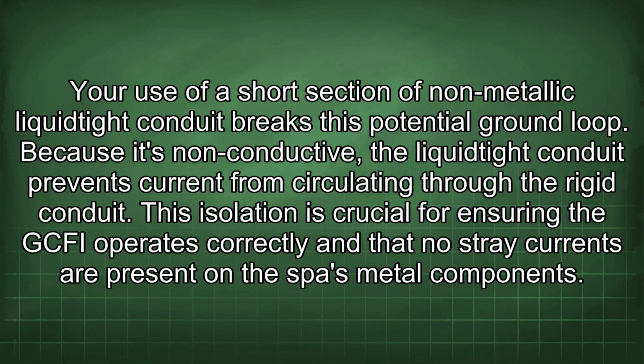Your use of a short section of non-metallic liquid-tight conduit breaks this potential ground loop. Because it's non-conductive, the liquid-tight conduit prevents current from circulating through the rigid conduit. This isolation is crucial for ensuring the GFCI operates correctly and that no stray currents are present in the spa's metal components.